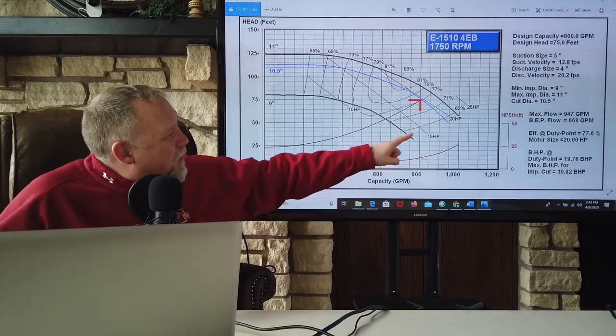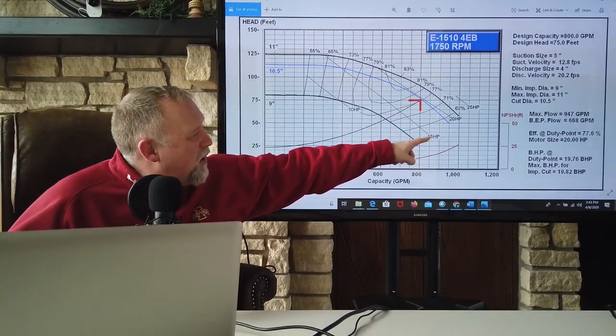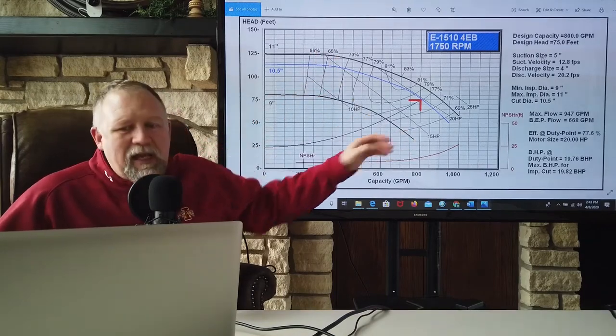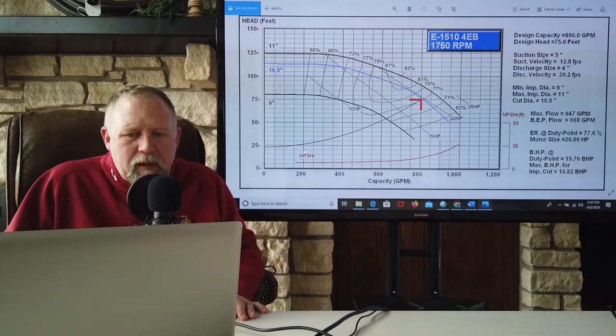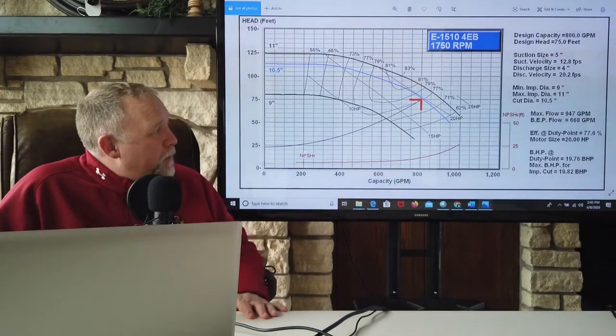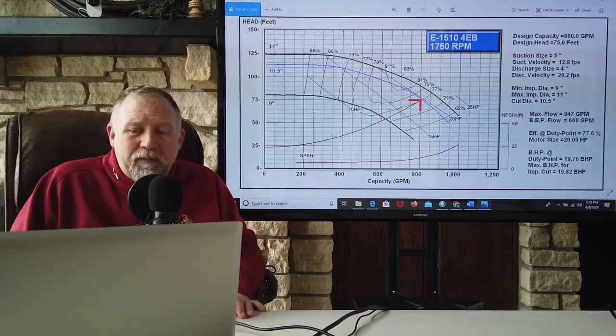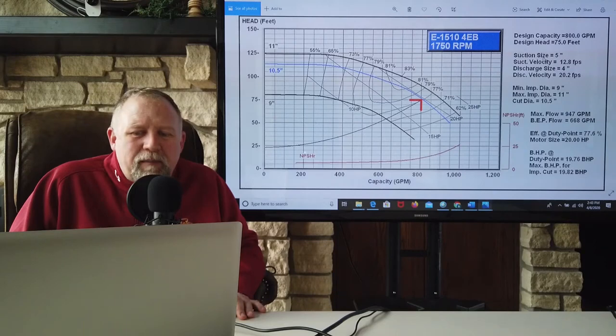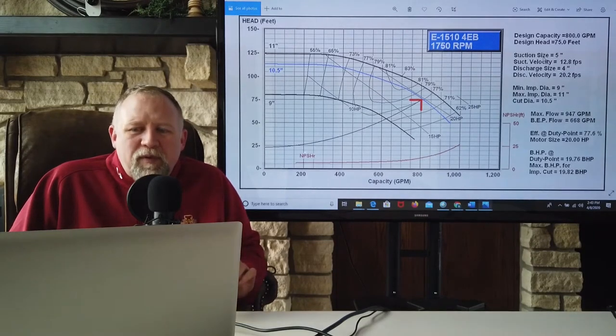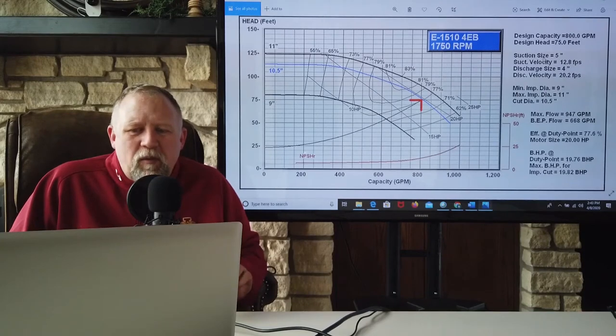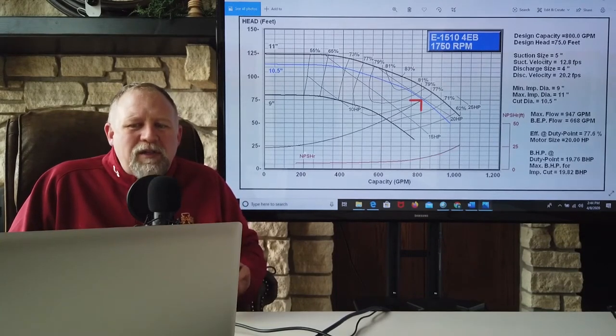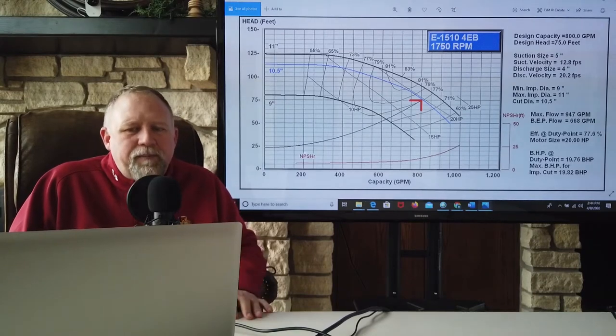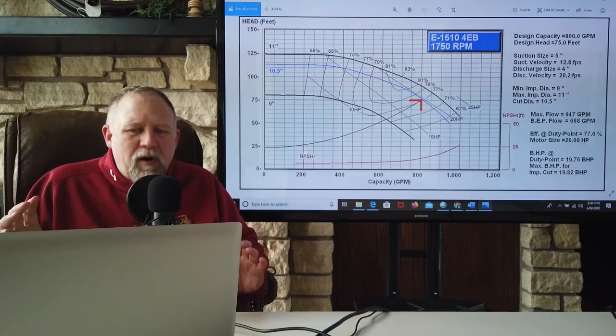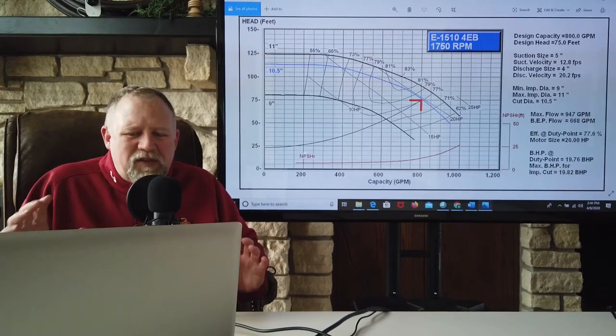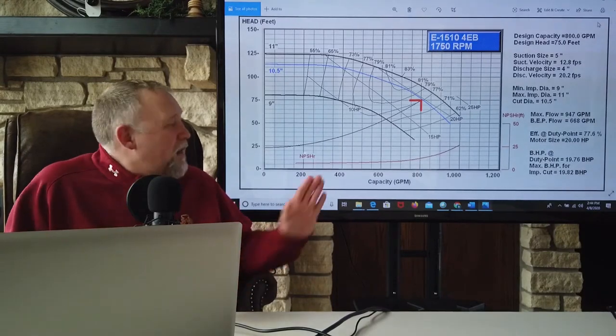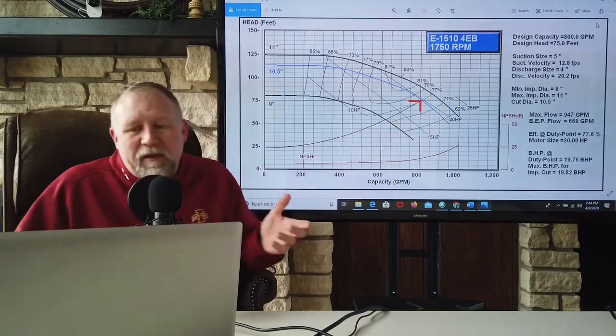And then these lines here, I want you to pay careful attention to these lines that start down here and go up here. These are lines of constant power. Now, is your pump going to operate right on one of those lines? Probably not. But those lines represent lines of constant power. In other words, those represent common motor horsepowers that we could actually purchase. We are not going to custom make a motor for your particular pump. You're going to buy a motor, and most likely you're going to buy a standard size, kind of off the shelf. And that's what these sizes are, this is a 15 horse, this is a 20, this is a 25.